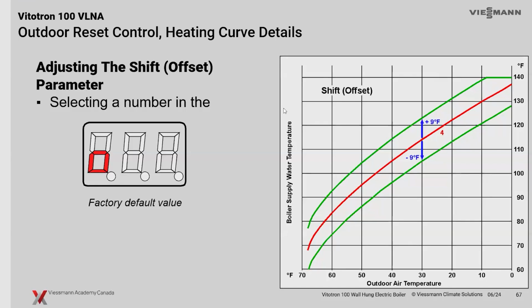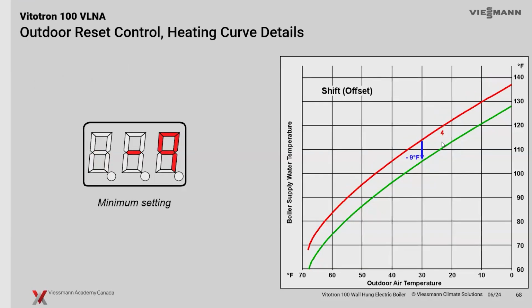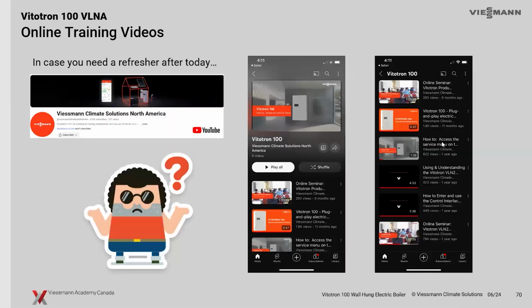And again, some guys will change their shift and slopes automatically. I tend to use the shift or offset more as after a year or so of operation, if everything's running well, I can start making incremental adjustments using the shift to kind of drop the temperature down a couple degrees. So the homeowner doesn't really notice it, but you're going to save a little bit of power because we're going to be using that much less juice during the heating season because we lower that supply temperature a little bit on that side. All right, so we go from +9 to essentially -9 Fahrenheit as a scale there.